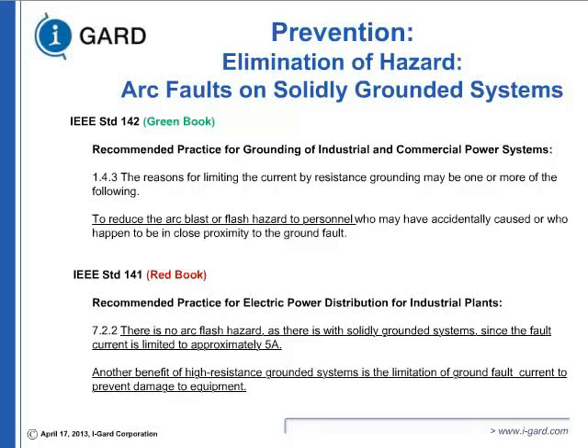Recommended practice, the Green Book, which is the premier grounding document, states that one of the reasons for limiting the current by resistance grounding may be one or more of the following. There are 3 or 4 given. We have just shown you one: to reduce the arc blast, the flash hazard, to the personnel who may have accidentally caused or who happen to be in close proximity to the ground fault, which you cannot avoid. The first fault is going to happen. Electrical faults happen very quickly.